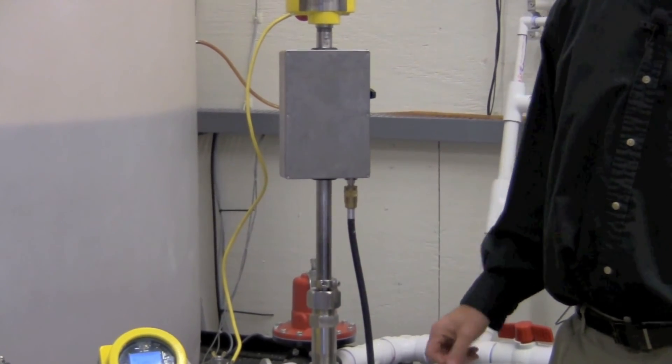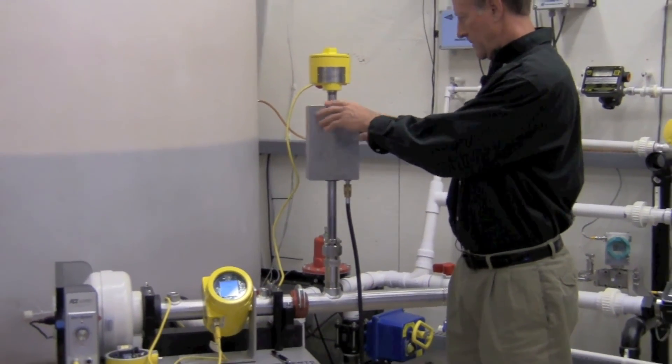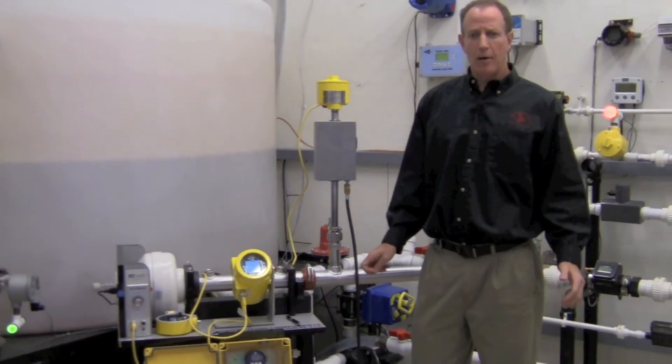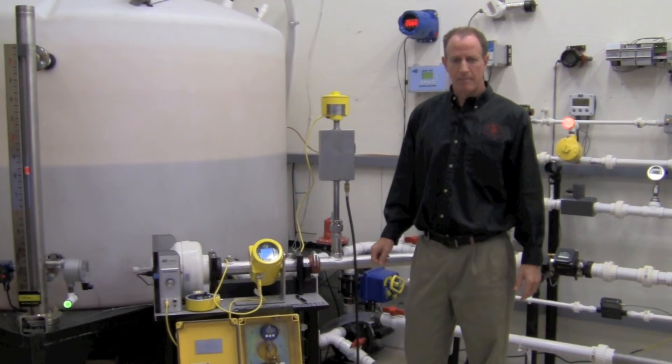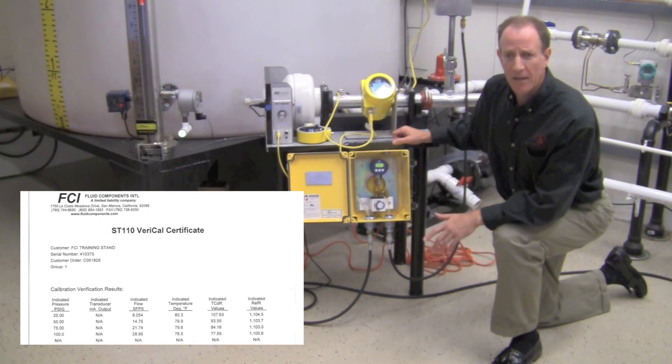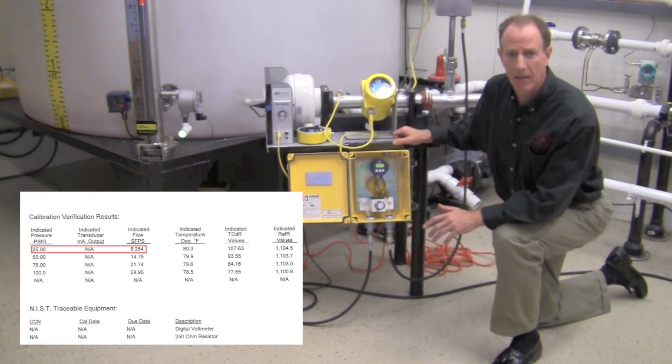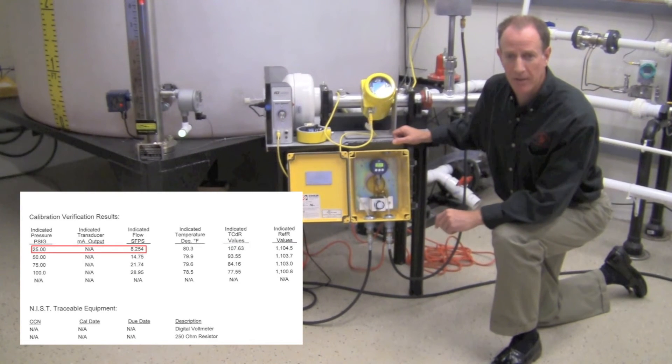Open the check valve. The nitrogen is now flowing across the sensor. FCI provides data at several pressure points. We'll check calibration at two points in this demonstration. Referencing the calibration documentation, we note that a pressure of 25 PSI should yield a flow reading of 8.2 feet per second.